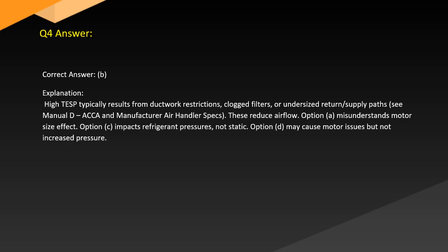Answer. Correct answer: B. Explanation. High static pressure typically results from ductwork restrictions, clogged filters, or undersized return or supply paths. See the manufacturer's air handler specs. These reduce airflow. Option A misunderstands motor size effect. Option C impacts refrigerant pressures, not static pressure. Option D may cause motor issues but not increased pressure.